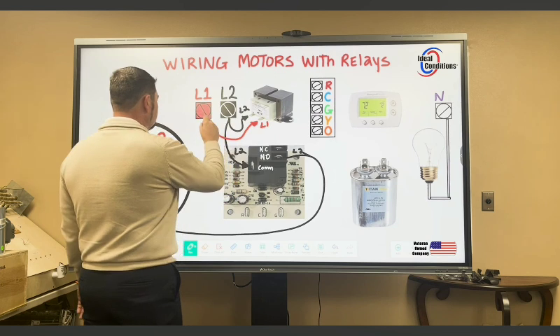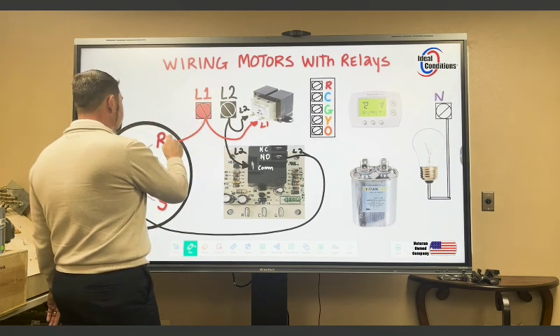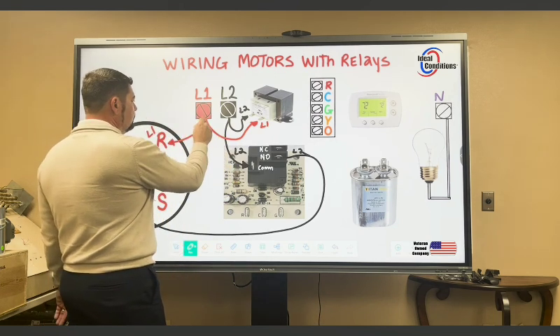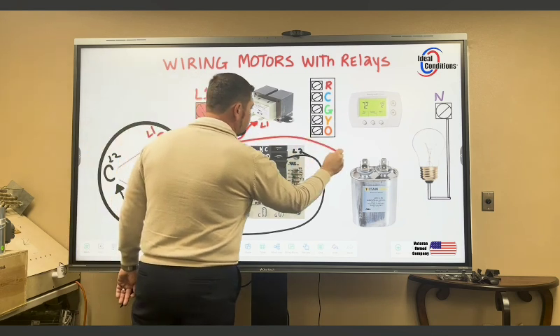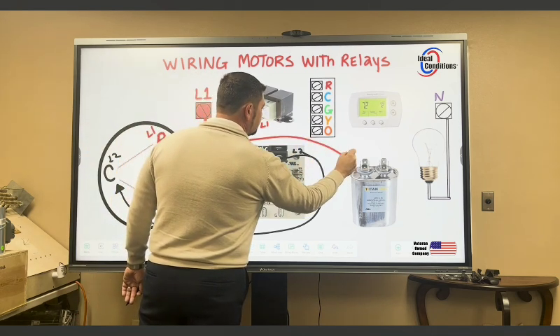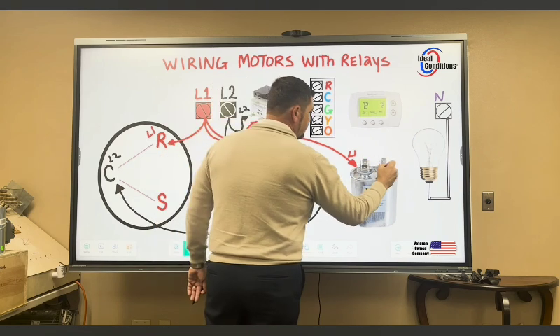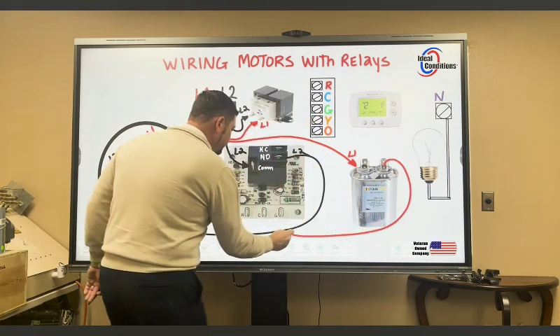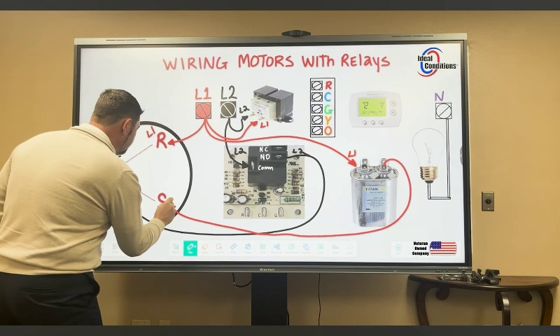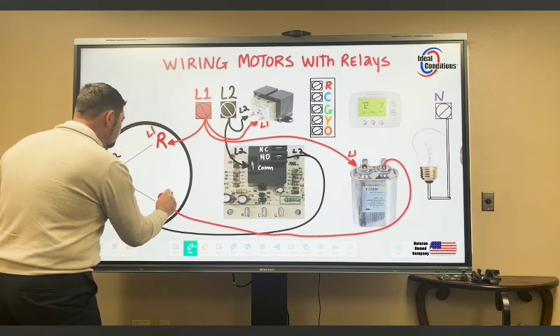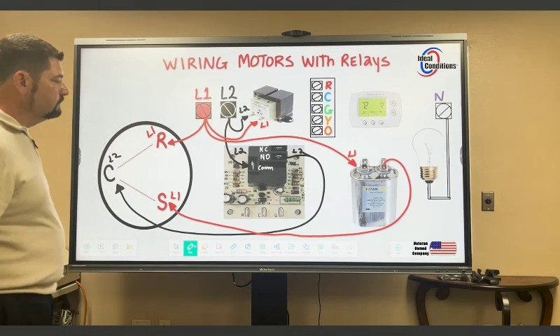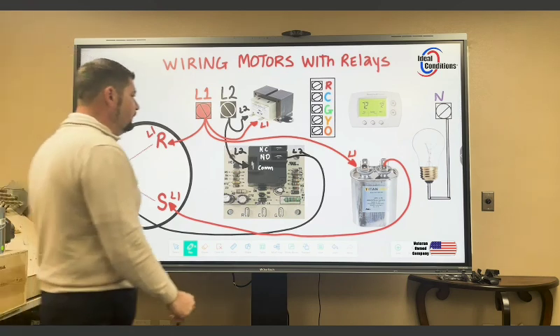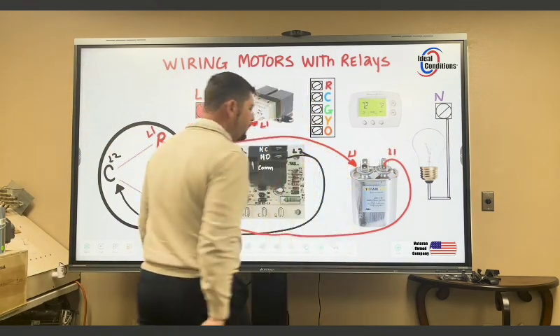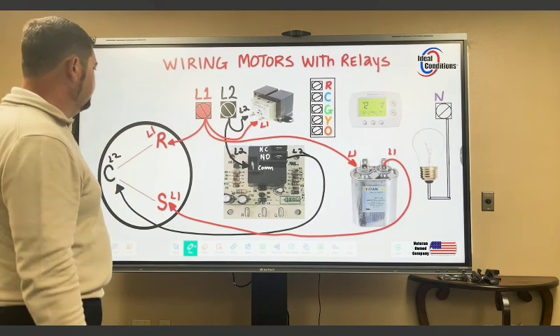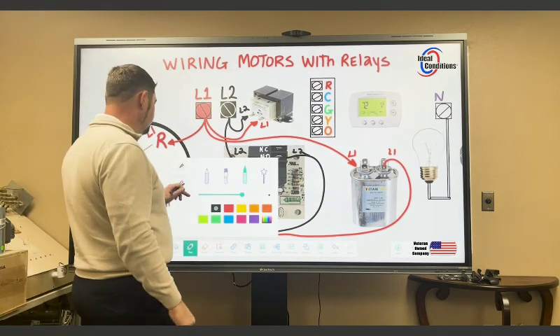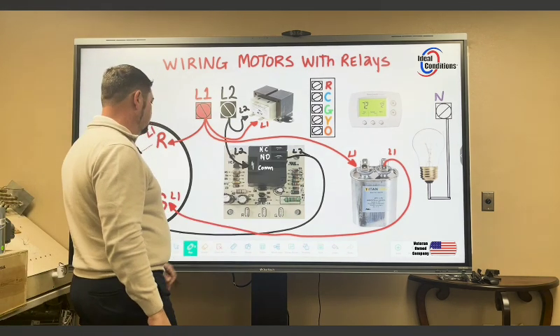I'm going to go ahead and start wiring up my motor, my run winding here. I'm going to go ahead and wire up my run capacitor. And then my third leg of power, even though it's single phase, so I can have polarity, will be on that start winding. And now it looks like everything is pretty much checked off. Everything's done there. The only thing that's left is the transformer and the rest of the low voltage.